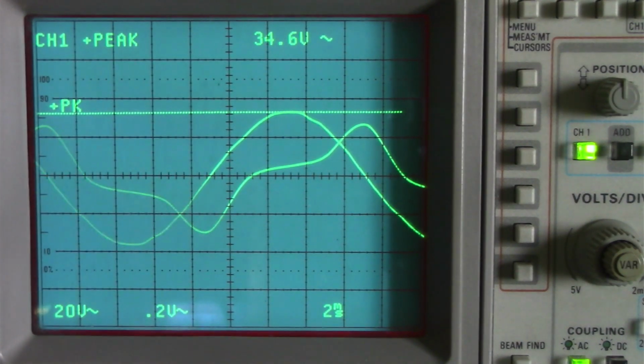As for the calculations, we see that this current waveform has a peak of about 1.4 divisions. And since the oscilloscope is currently set to 0.2 volts per division, that means we have 0.28 amps of current in the transformer. You'll recall our previous conversation where we had 10 wraps through the aperture of that transformer. Because of that, there's a one-to-one relationship between the voltage as measured on the oscilloscope and the actual current in the device. Now, watch what happens when we increase the voltage.